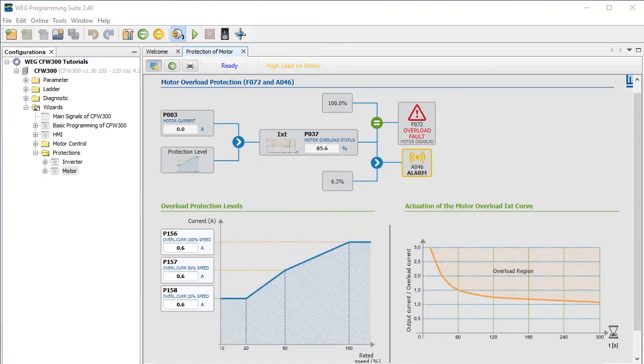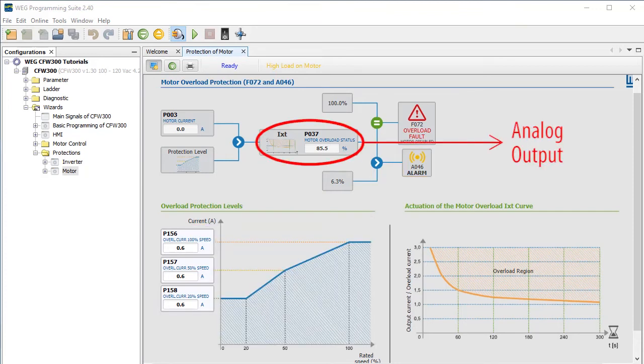A couple of side notes. First, you can send this IXT signal to an analog output so you can watch it in real time on a scope. This WPS software is great, but it does take time to update the screen, so you don't actually see everything that happens. When you watch it on the scope, you get a much better feel for exactly what's happening and when.